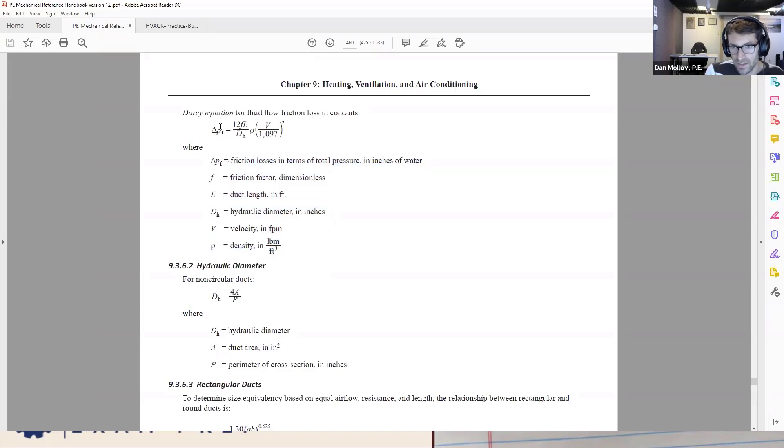And provided we do that, the answer kind of magically comes out to inches of water, which wouldn't necessarily be the case if we didn't do a bunch of unit conversion along the way. So the name of the game becomes: we're going to put in a dimensionless friction factor, a duct length in feet, a hydraulic diameter in inches. And as long as we follow all these rules with the units on the input side, it should theoretically come out to give us inches of water for that friction loss.